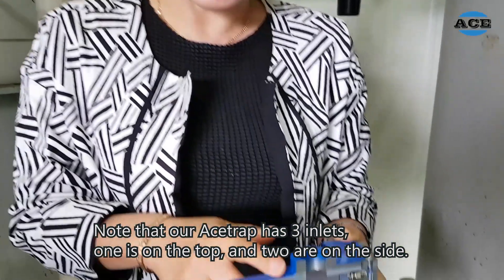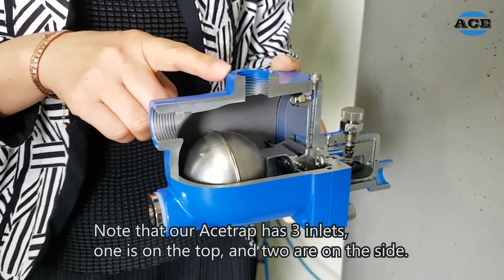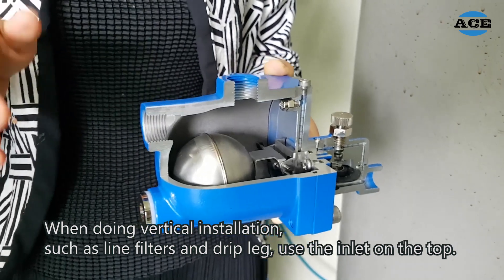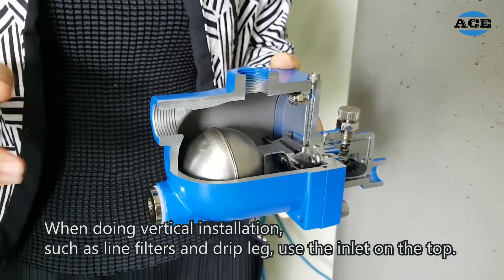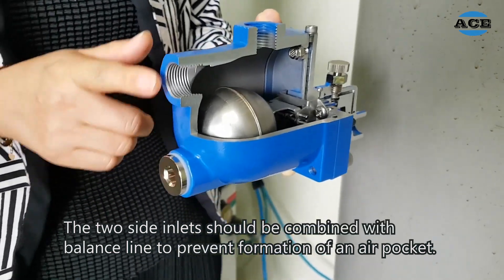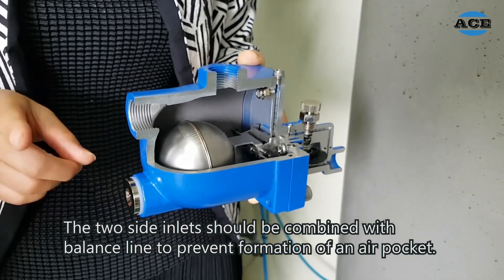Note that our Acetrap has three inlets. One is on the top, two are on the side. When doing vertical installations such as line filters and drip leg, use the inlet on the top. The two side inlets should be combined with the balance line to prevent formation of air pockets.